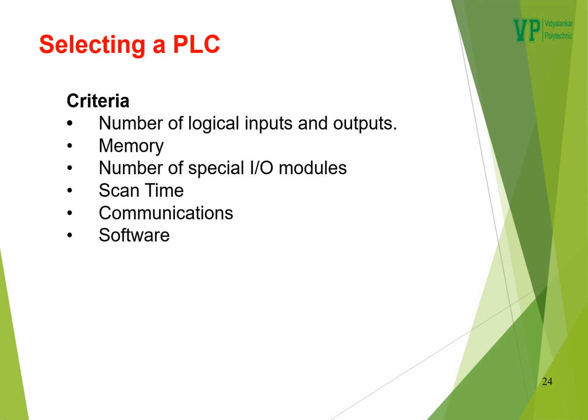It is also essential to know the memory size of your PLC, because it is the memory where your ladder diagram is going to be placed. Besides this, it is also important to know the number of inputs and outputs that you would need for your project. And you should also know if your project needs analog input and analog output, and accordingly, you could buy a PLC. The scan time is one of the most important specifications of a PLC, which decides the speed of a PLC.